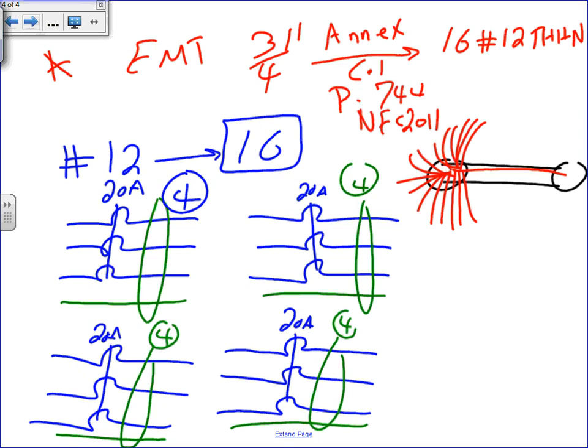So people were zapped, number one. And number two, we were burning equipment, because people think that because we turned one of them off, I can go and open that neutral. Oops. Not knowing that this neutral is shared by the other two circuits. And like Chad did one time, you burned the fan. Open neutral. Remember the whole issue of the open neutral? Safety. You compromise a little bit on reliability though, because now if one of them trips, the others could trip.